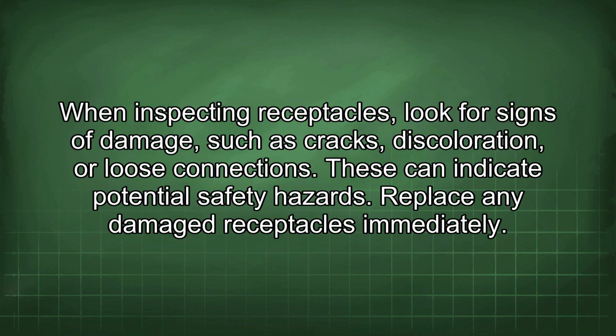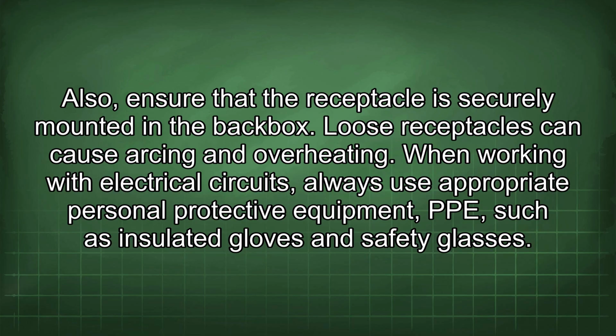When inspecting receptacles, look for signs of damage, such as cracks, discoloration, or loose connections. These can indicate potential safety hazards. Replace any damaged receptacles immediately. Also, ensure that the receptacle is securely mounted in the backbox. Loose receptacles can cause arcing and overheating.